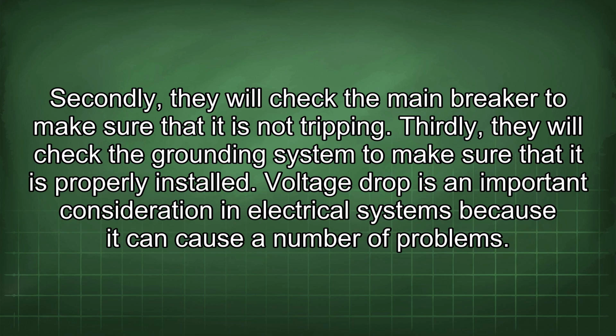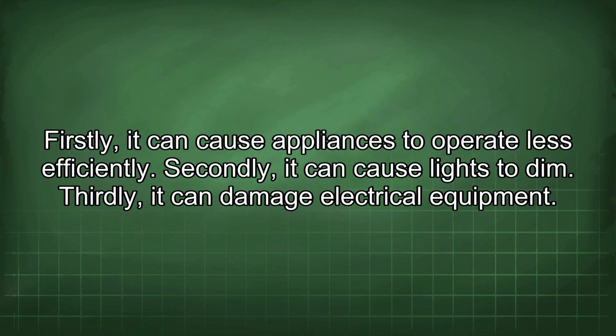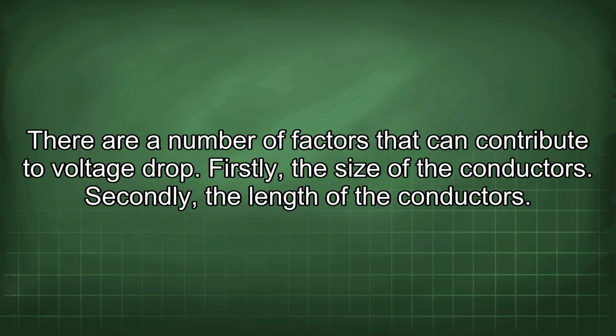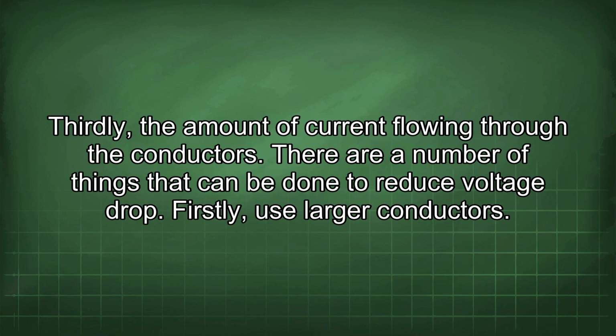Voltage drop is an important consideration in electrical systems because it can cause a number of problems. Firstly, it can cause appliances to operate less efficiently. Secondly, it can cause lights to dim. Thirdly, it can damage electrical equipment. There are a number of factors that can contribute to voltage drop. Firstly, the size of the conductors. Secondly, the length of the conductors. Thirdly, the amount of current flowing through the conductors.